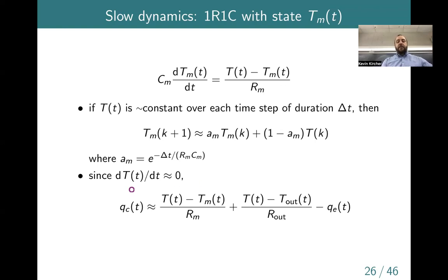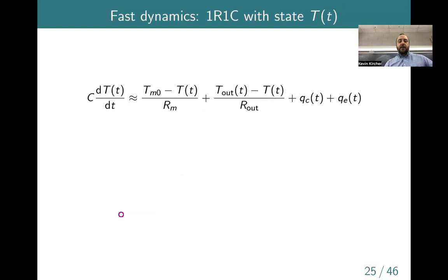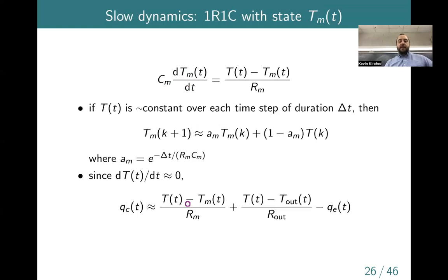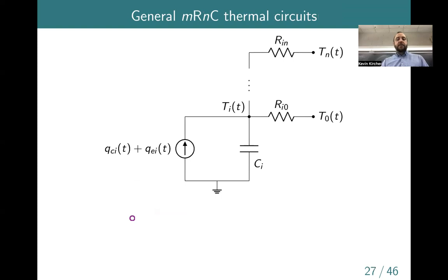And then on the air side, we're assuming basically that its time derivative is almost everywhere equal to zero. That when it changes, it basically changes instantaneously. So this is sort of a quasi steady state model. And so if that's the case, then we had our governing equation for the air, essentially this thing here. We take the left-hand side and set it equal to zero, and then we solve for T, and we get this equation here. Sorry, we don't solve for T, we solve for Q, which gives us essentially the heat or the cooling that's being injected or extracted from the space. And so we're assuming basically that this thing here is going to, again, adapt kind of instantaneously to changing boundary conditions. And I'll show what this stuff looks like in a minute.